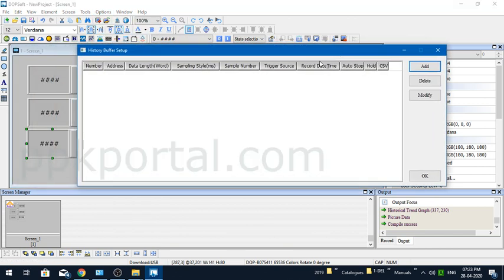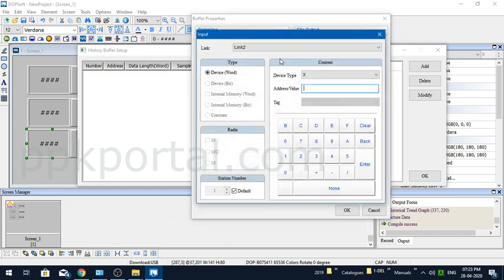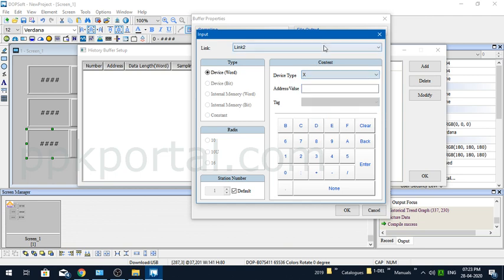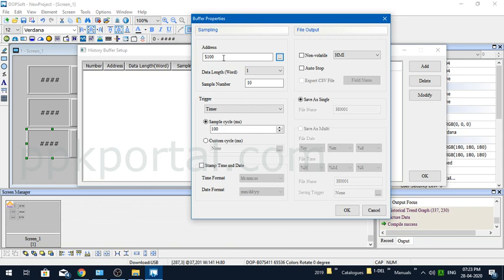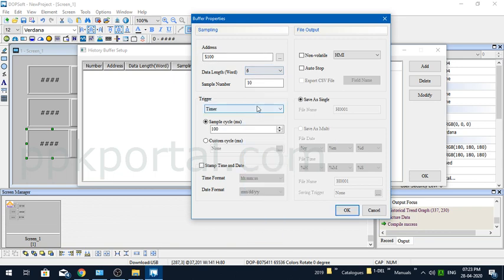You have to create a buffer and remember your buffer ID. Now declare the starting address. Whenever you want to do data logging on the HMI, try to allocate all the data to a consecutive address range so it will be easy to work. Here in my case, it's the internal memory, so I'm putting a length of six because I'm considering $100, $101, $102, $103, $104, $105, $106.